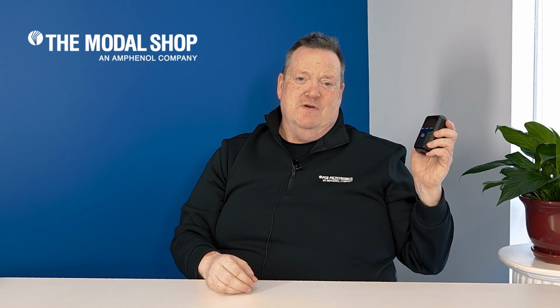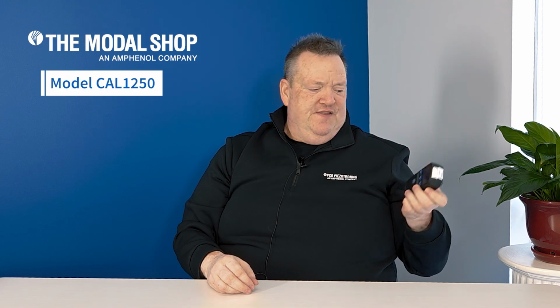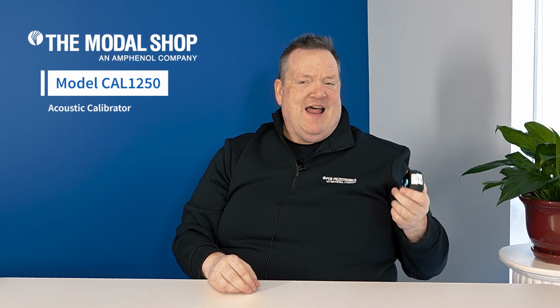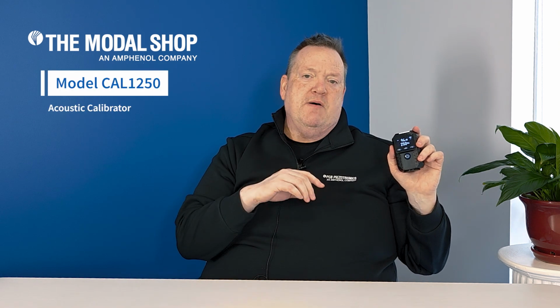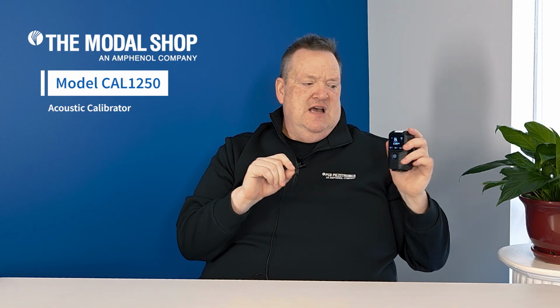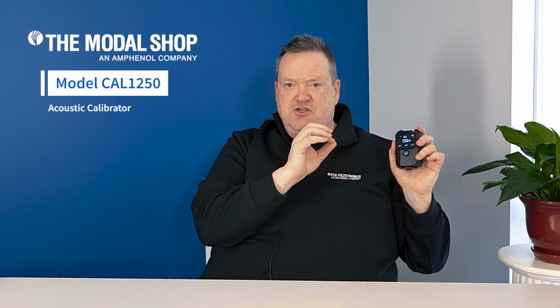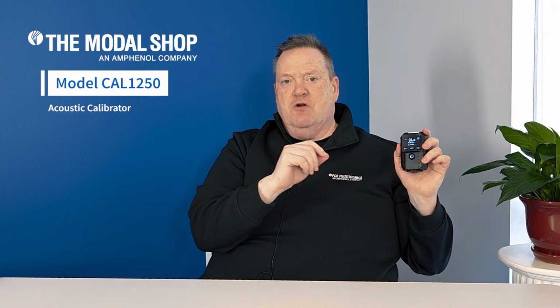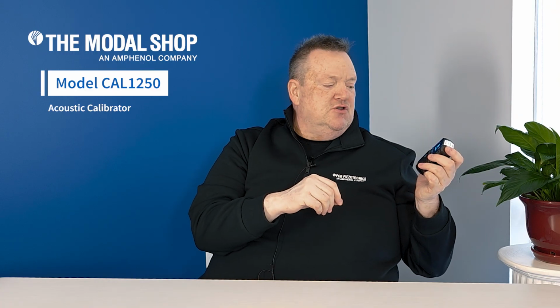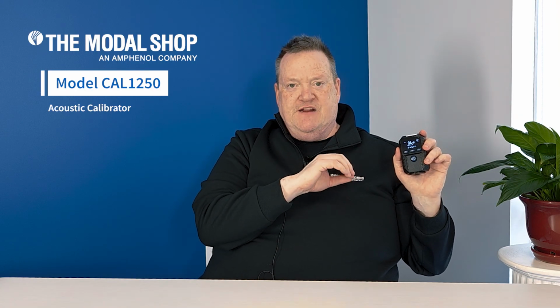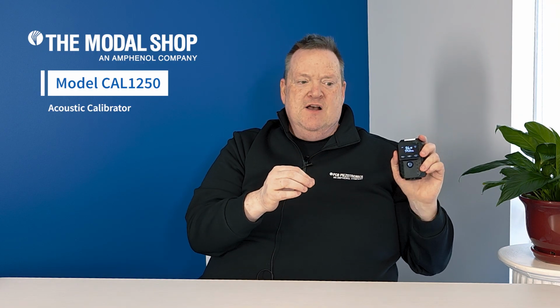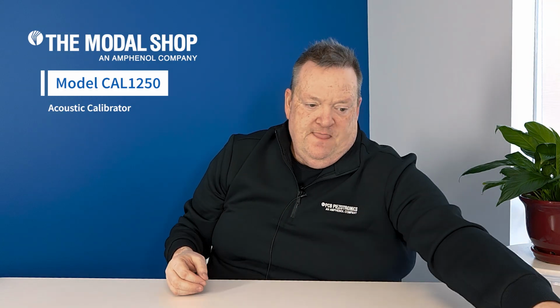The sound calibrators have been revamped by Larson Davis recently. The Cal 1250 is the flagship in the line. What's new is it allows not just a frequency change - you can calibrate it at 250 or 1,000 hertz - you can also vary the amplitude from 94 to 114 dB. So it gets you a lot more flexibility in your calibration options.